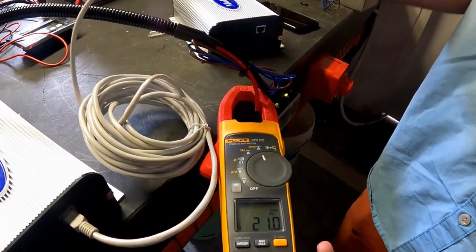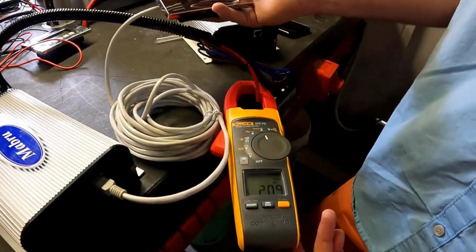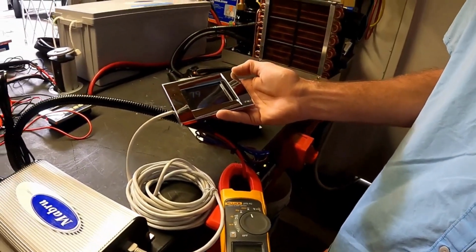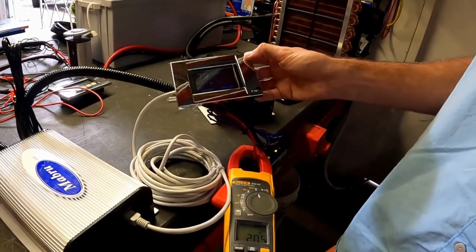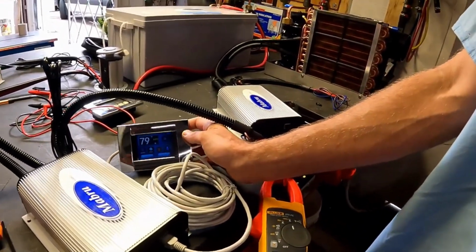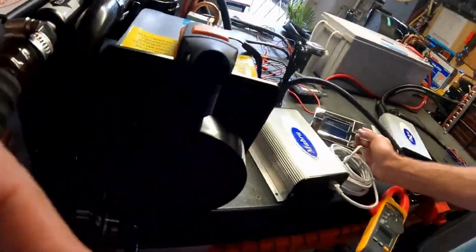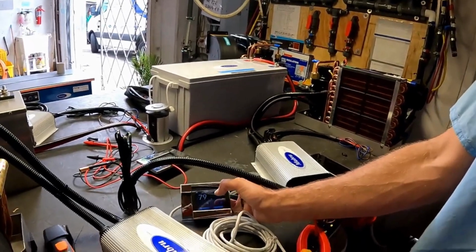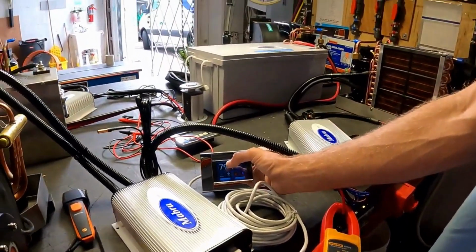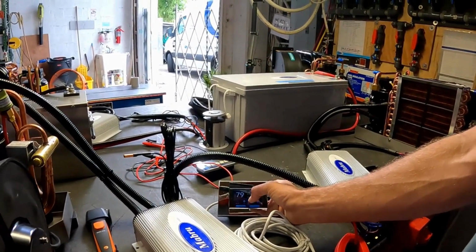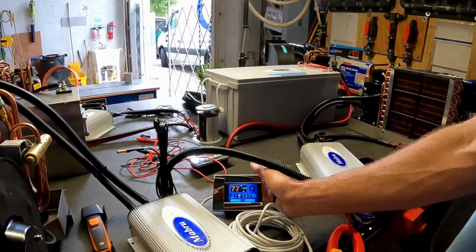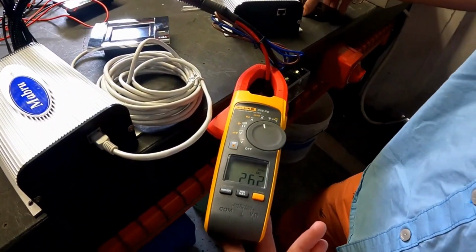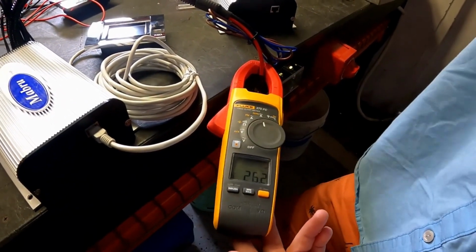So the idea behind this unit is that the unit will almost never be shutting down. This is another demonstration of efficiency. Absolutely. We are going to request this of our students. We have basically the same input temperature and the same discharge temperature, and the consumption decreased dramatically. Wonderful. Now the consumption just went back up because the return temperature just went up a little bit. So if I put it back up a little bit closer, the amps start to go down and down.